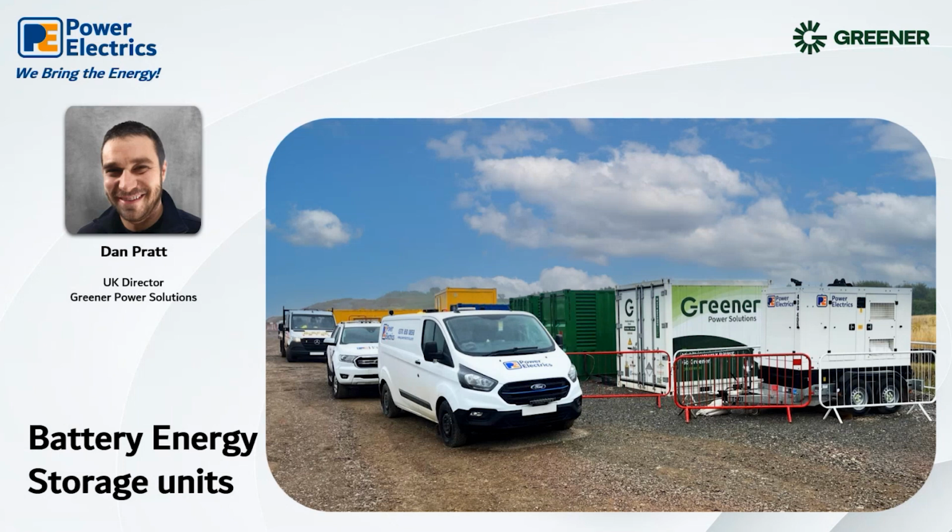Finally, the other thing is that it's now possible to parallel Greener battery systems, which I don't think's been a thing historically. Yeah, sure. So we've run projects utilizing up to 10 of these batteries that are able to deliver 3 megawatts of peak power with 4 megawatt hours of energy storage. And because of this paralleling capability, that also means we can provide backed up or redundant power supplies from our batteries, as you would have done historically with a pair of synchronizing generators.